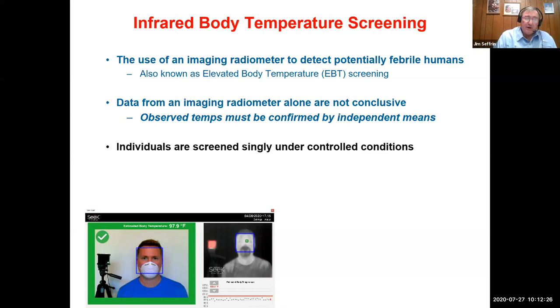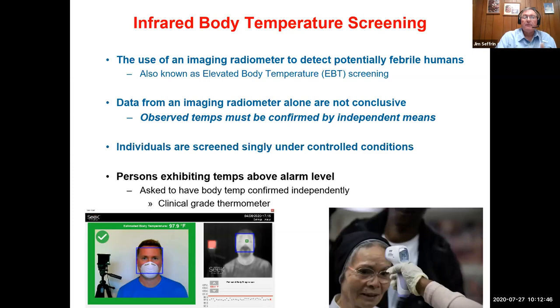For a number of reasons, which are too numerous to go into right now, there's a lot of equipment out there that's not being used properly, and a lot of equipment which just is not effective. So in order to do this properly, that is using a thermal imager for elevated body temperature screening, persons are screened singly under controlled conditions. Anyone who is exhibiting a temperature above a predetermined alarm level is then asked to have their body temperature confirmed independently utilizing a clinical grade thermometer. That thermometer can either be a contact thermometer or, because of the challenges associated with sanitation, a non-contact or infrared thermometer is typically used. We'll talk about both of those techniques in just a little bit.